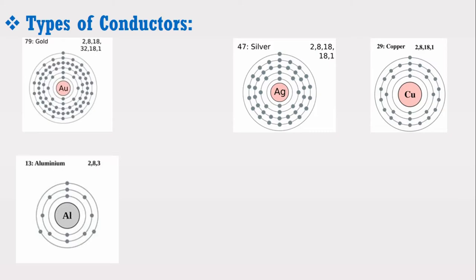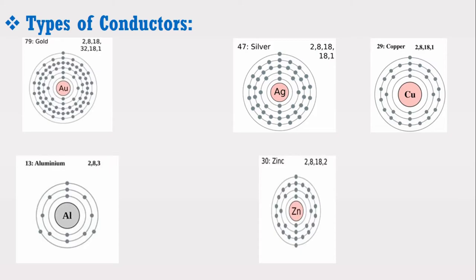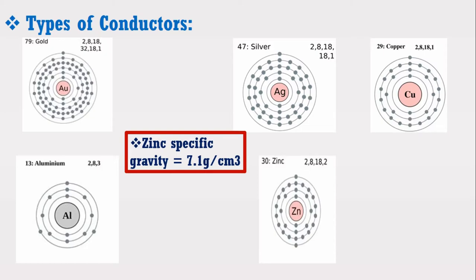A question may arise: is there any element that has two electrons in its outer shell? Two electrons in the outer shell means it will have higher conductivity than aluminum which has three electrons. The answer is yes — there exist some elements with two electrons in their outer shell. For example, zinc has two electrons in the outer shell. However, it is not used in transmission lines because the specific gravity of zinc is very high, almost 7.1 grams per centimeter cube. Due to this high specific gravity, its weight will be very high, which requires poles and towers of greater strength to carry its weight, further increasing the total cost of the transmission line. Therefore, zinc is not used in the transmission line.